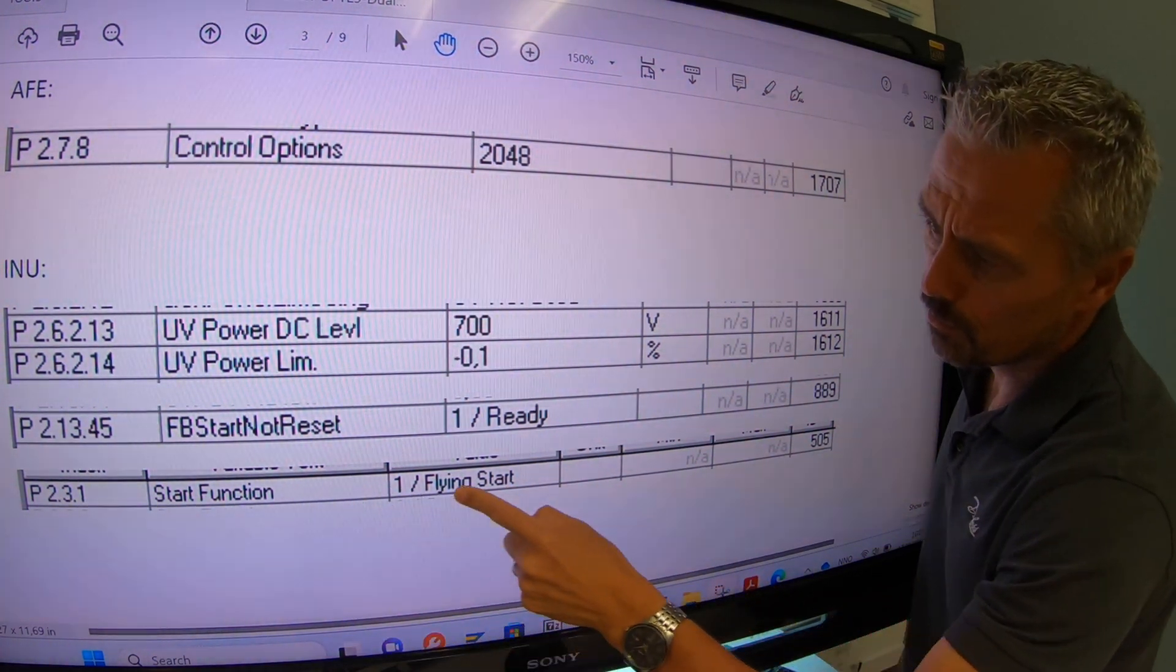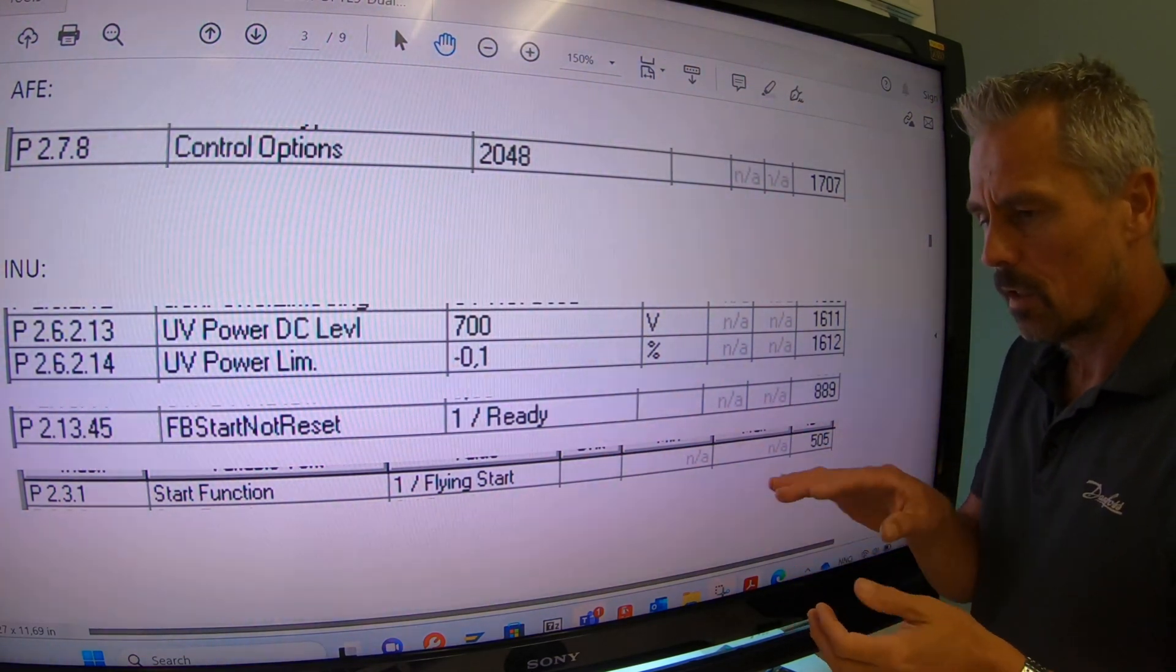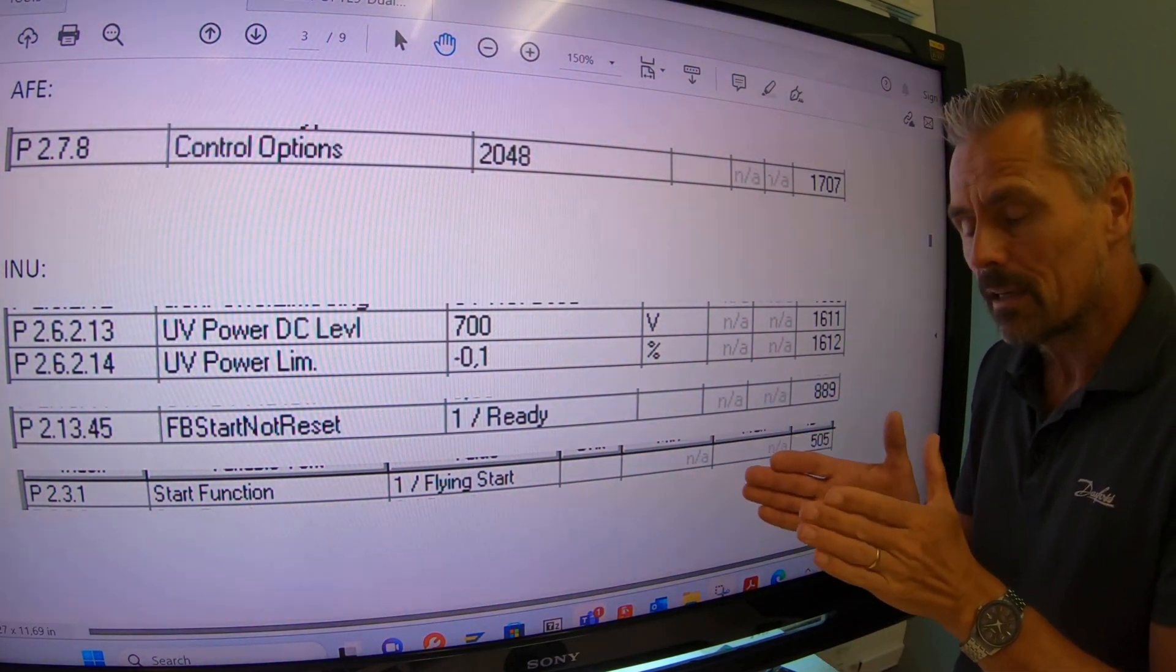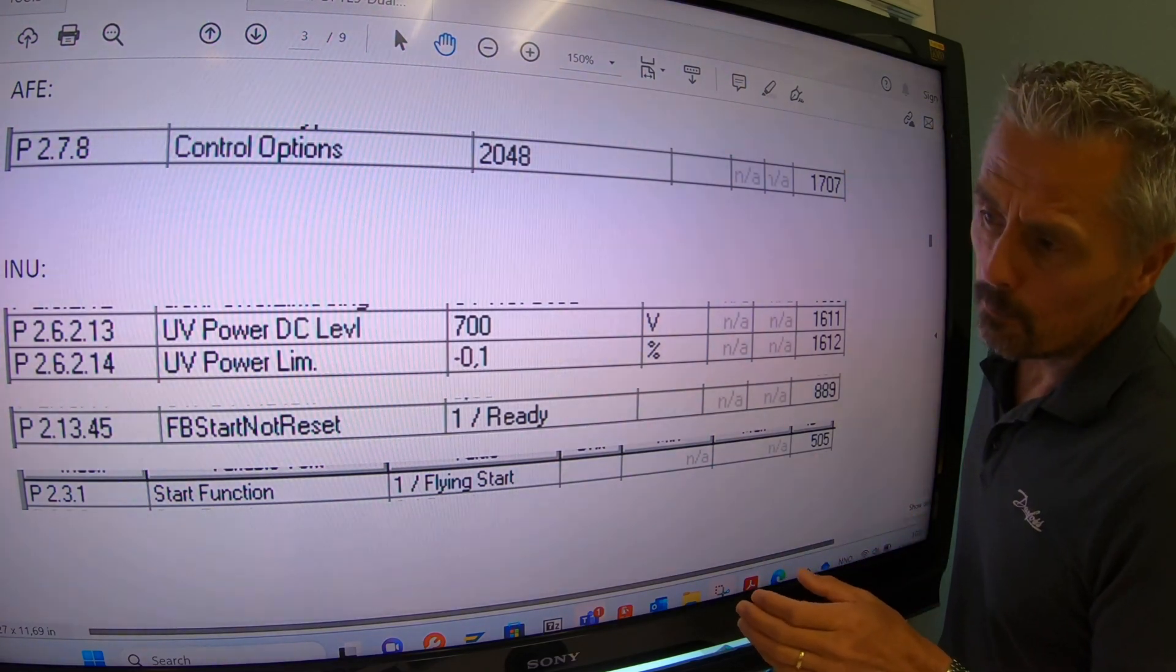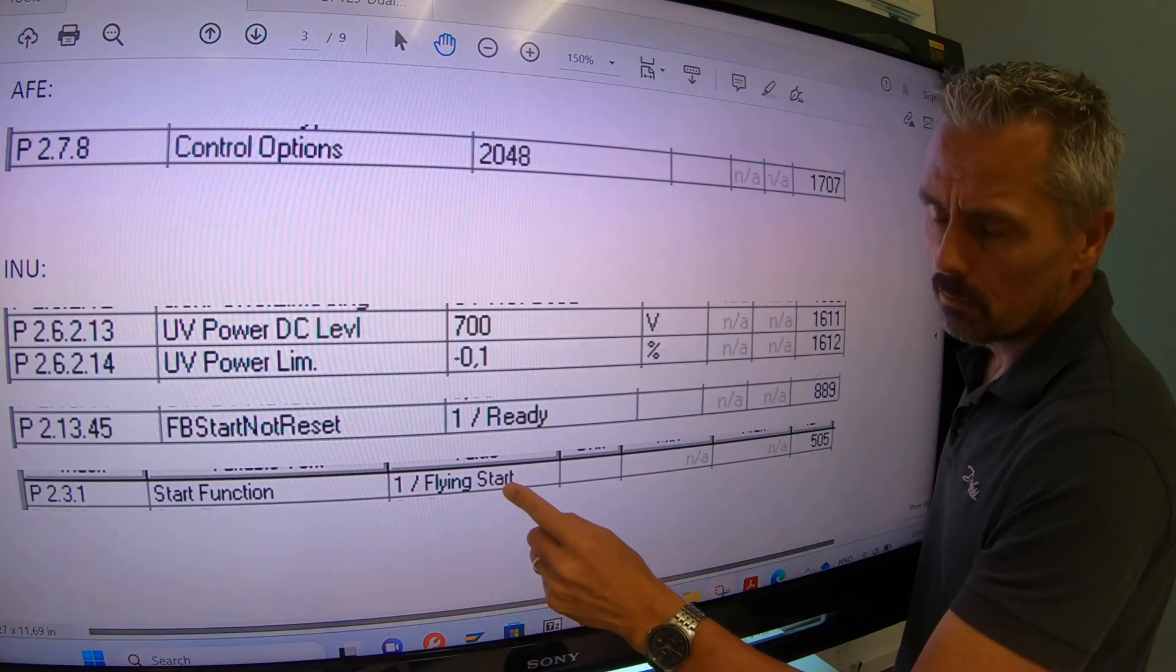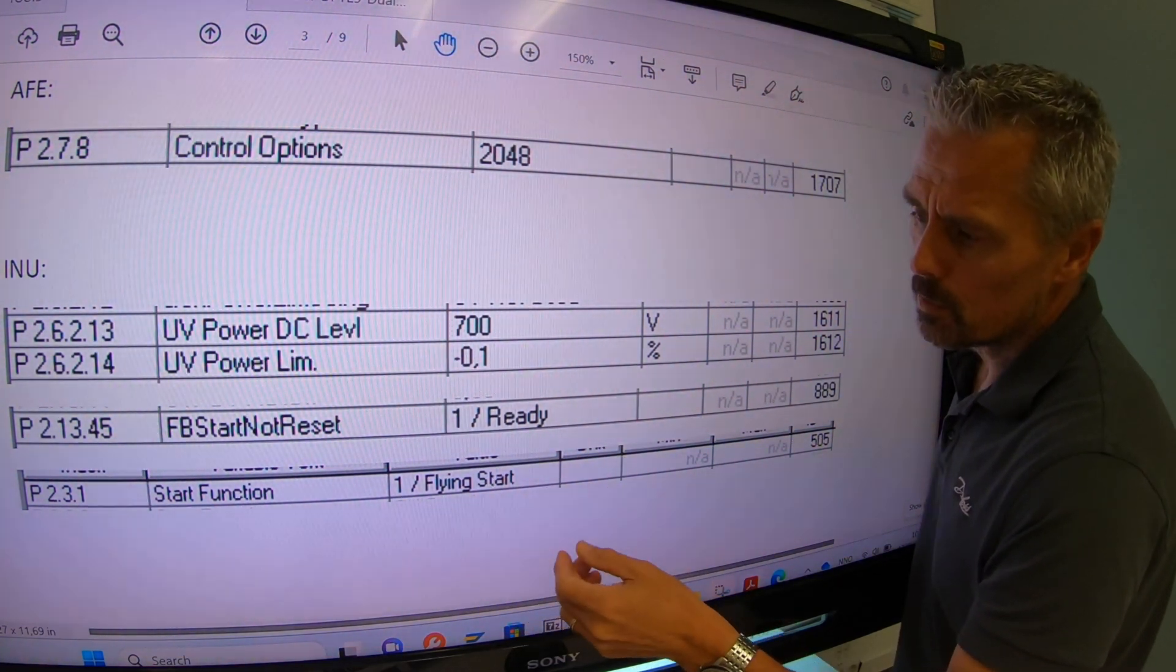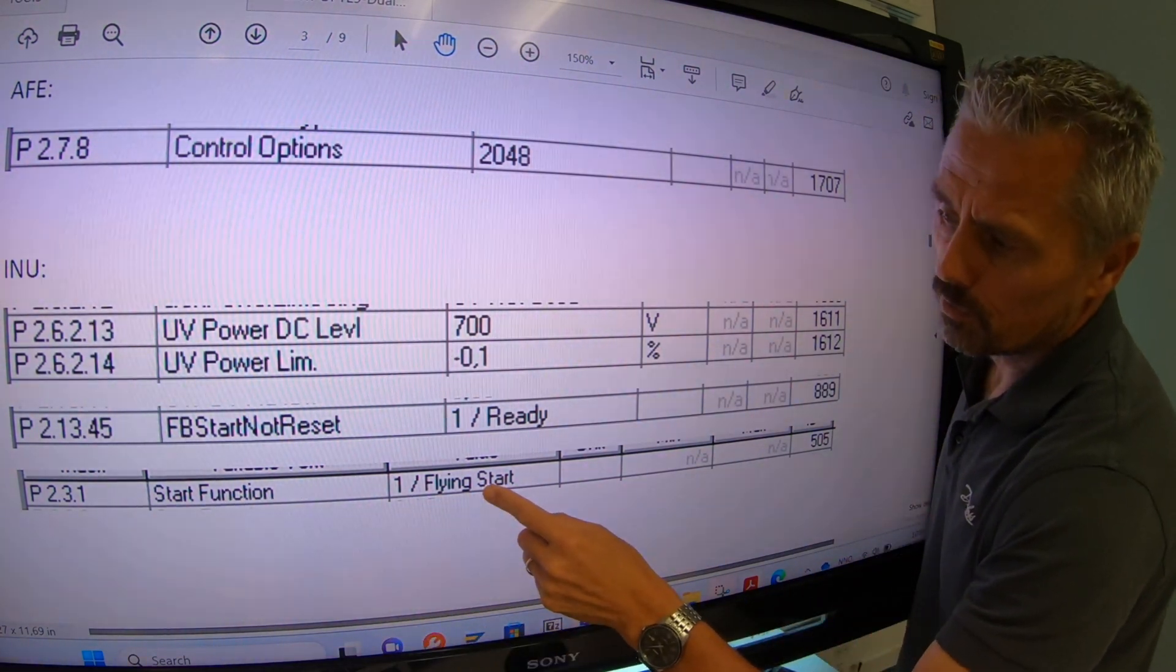And also flying start, the start function to flying start because most likely the shafts will be rotating. Especially if the blackout is very short, then you have rotating shafts. In closed loop, the flying start will be active anyway. But if it's an IF start or an open loop start, then this should be set to flying start.